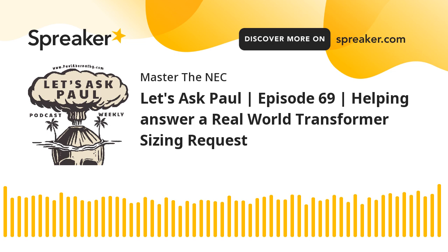One of your other questions here was, what size of primary disconnect, fused or non-fused? I think I kind of covered that already when I discussed the rules here. For that, if it's a 45 kVA, it'd be a 70. If it's a 30 kVA, it'd be a 45. That type of thing. So I think I've already covered that one.